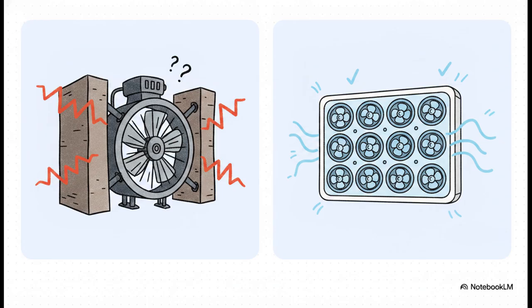Well, the old way relied on these massive utility fans, or vane axial fans, paired with highly restrictive sound traps. The problem is those required really high static pressure just to force the air through, which meant the system had to work harder and, you guessed it, louder. The new, much smarter practice is to completely rip out those old fans and sound traps and drop in a modern fan wall system. These fan walls are unbelievably quiet by design and run so much more efficiently without needing those old high-pressure sound traps at all.